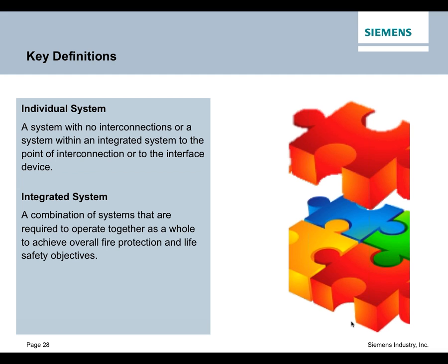You'll also see some additional definitions for your reference on what that individual system is. That's what we traditionally had, the fire alarm panel that just sat there and didn't interconnect with anything else. That's your individual system. The minute you have the fire alarm system, sprinkler system, the HVAC system for smoke control, and maybe security for door locking and unlocking, you now have an integrated system that needs testing in a proper way.